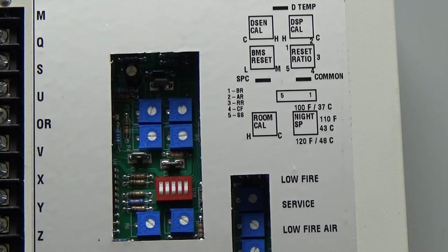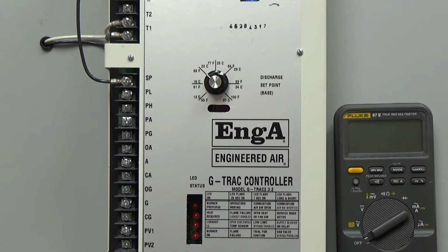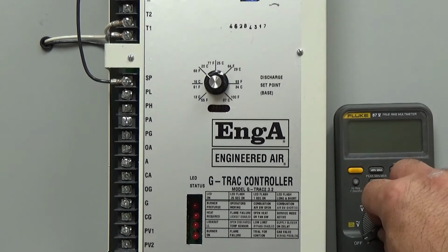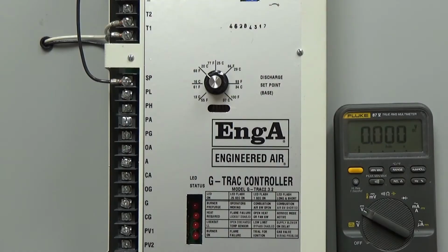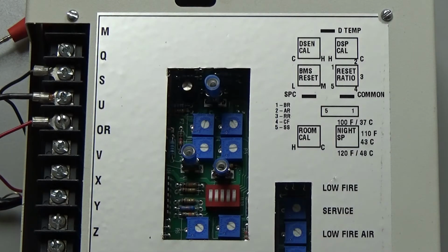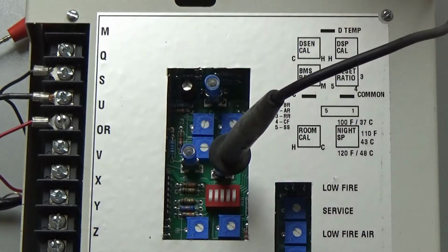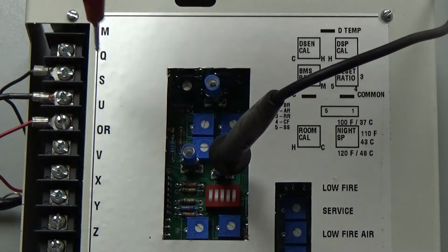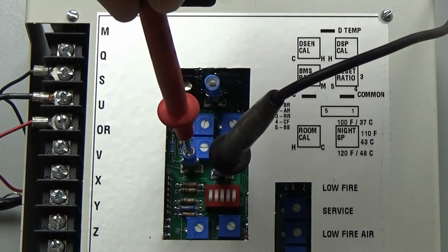Once you have determined the type of set point that is controlling the GTRAC2, locate the 3 test pins in the large cutout on the board. These 3 test pins will give you a readout of your final calculated set point and discharge sensor temperature. With the GTRAC2 powered, set your voltmeter to volts DC. Next, take the common lead of your multimeter and set it on the common test pin. Then, take your positive lead and set it on the test pin labeled SPC.